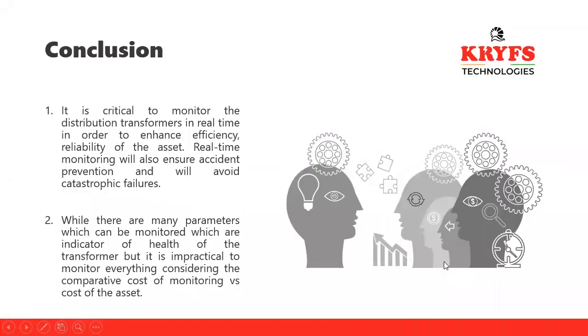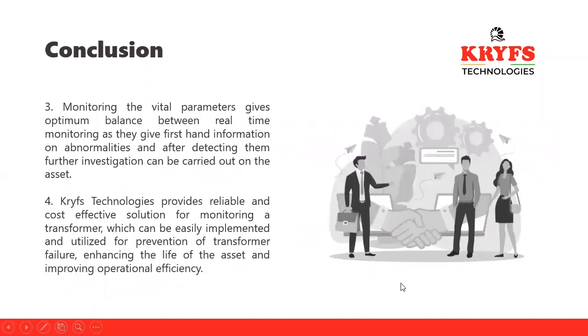So, conclusion: it is critical to monitor the distribution transformers in real time in order to enhance efficiency and reliability of the asset. Real-time monitoring will also ensure accident prevention and will avoid catastrophic failures. While there are many parameters which can be monitored, which are indicators of the health of the transformer, it is impractical to monitor everything, considering the comparative cost of monitoring versus cost of the asset. Monitoring the vital parameters gives an optimum balance, as they give first-hand information on abnormalities, and after detecting them, further investigation can be carried out on the asset.